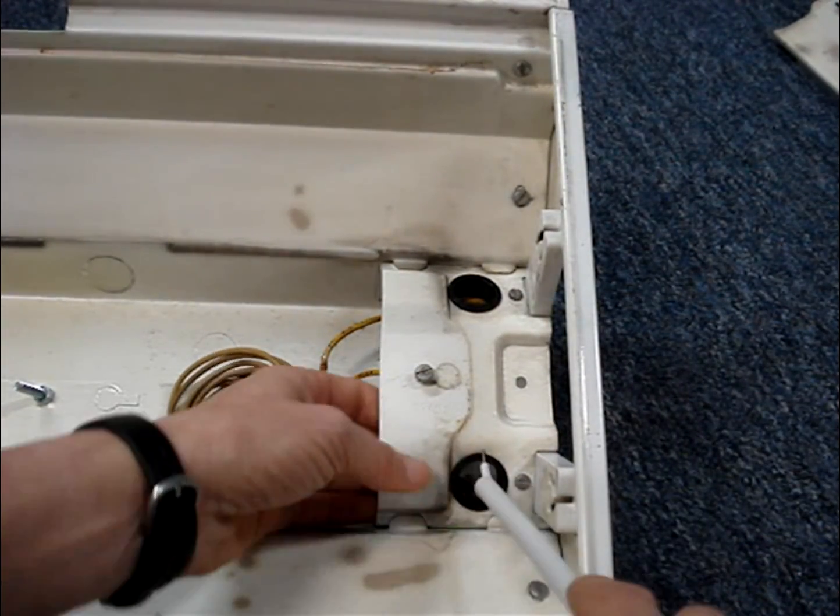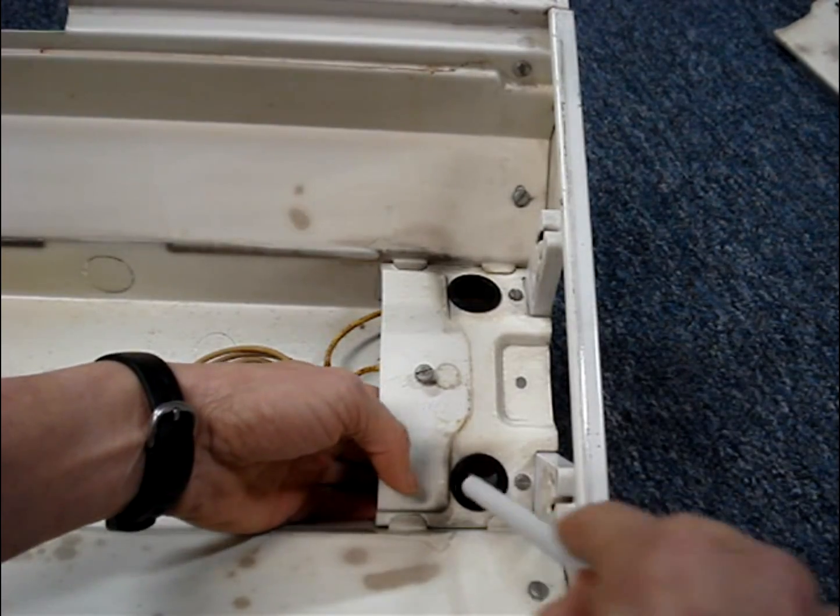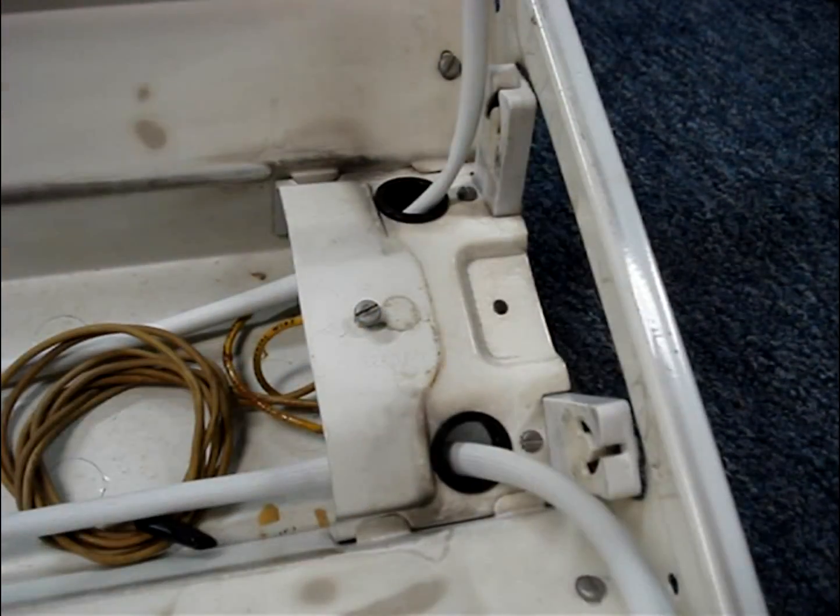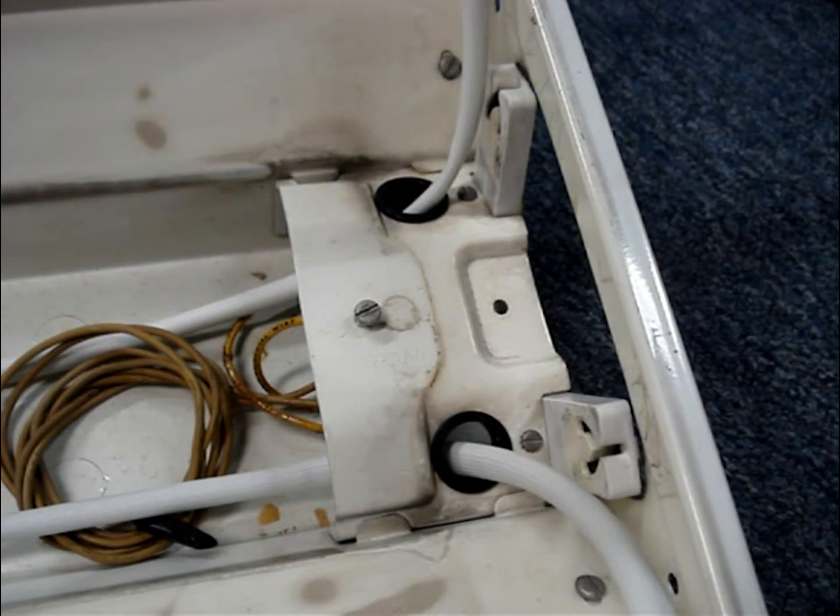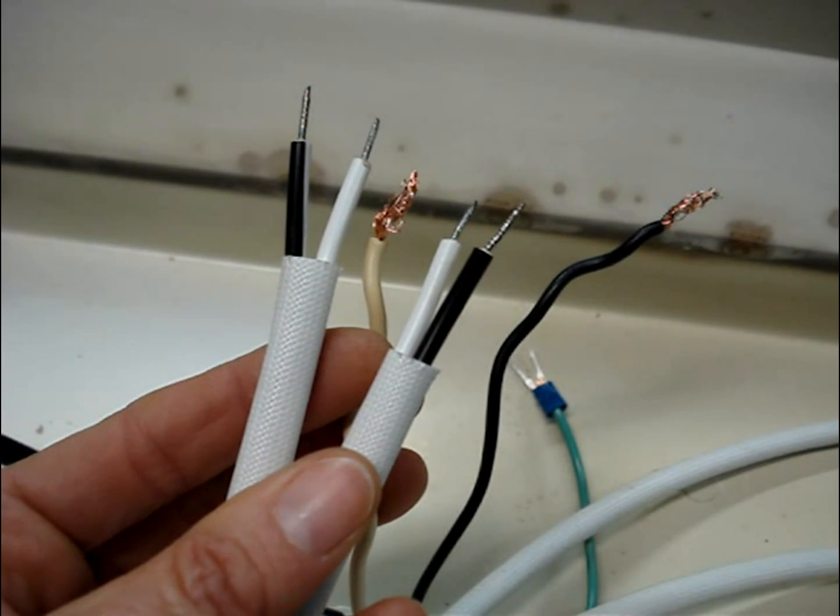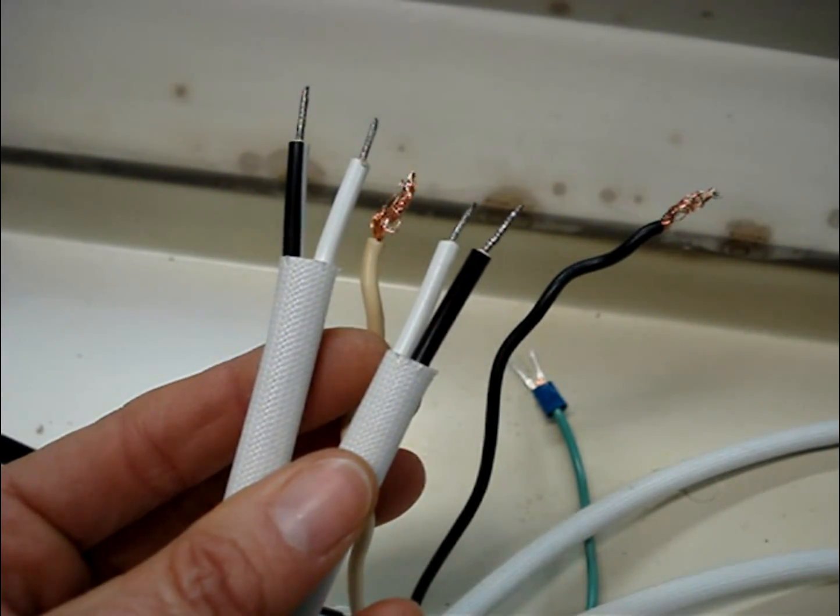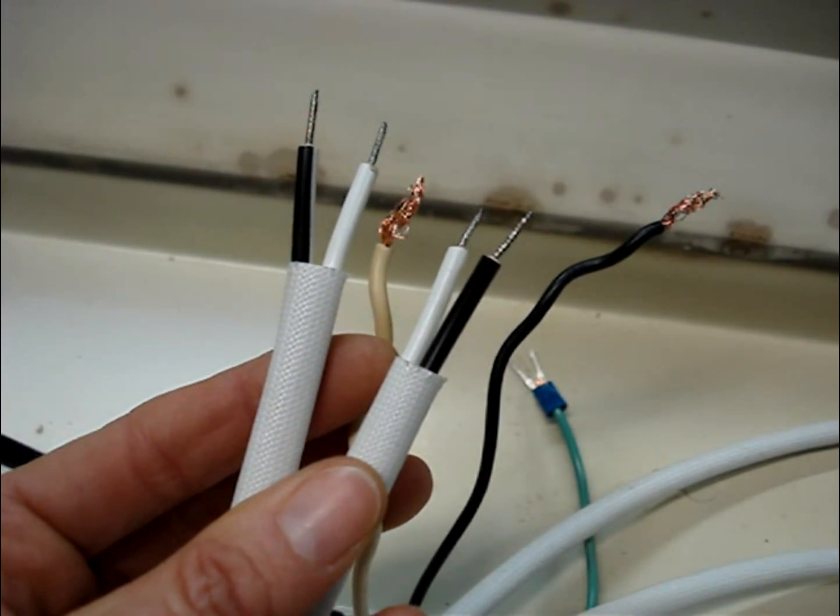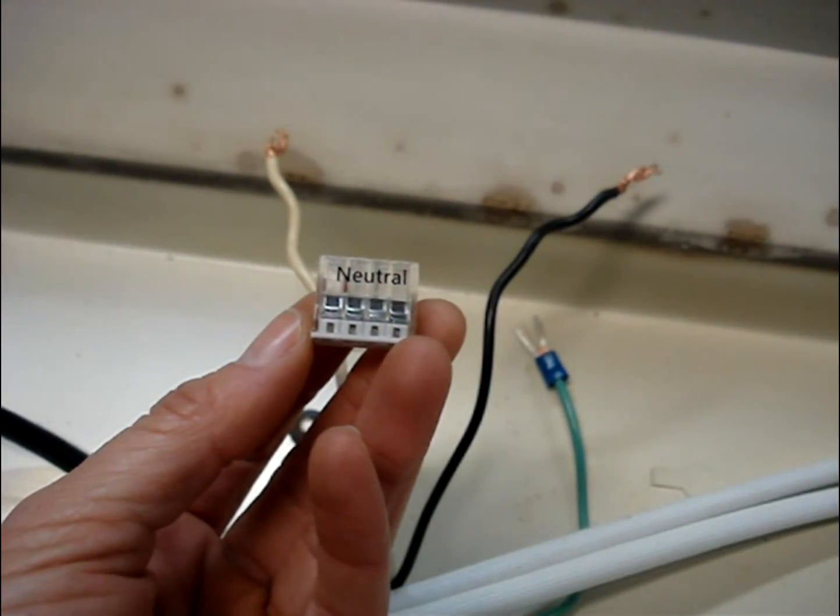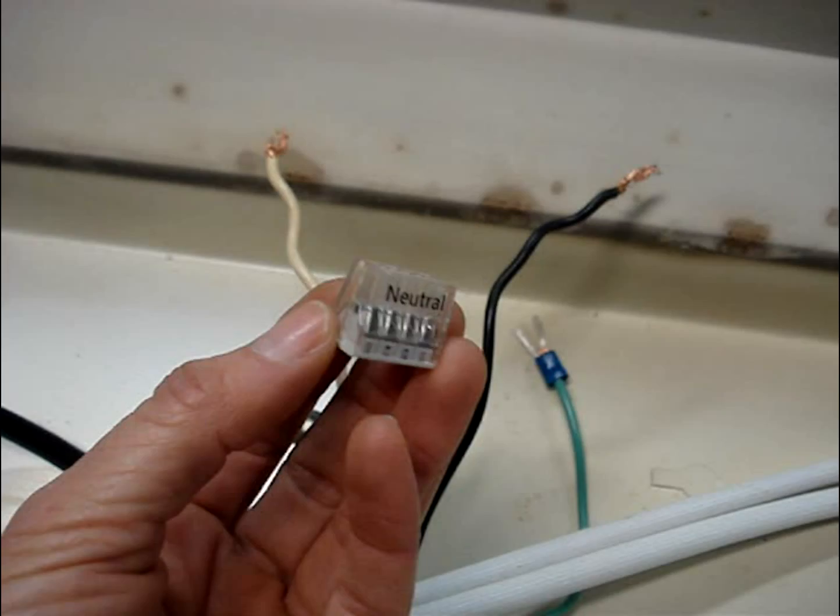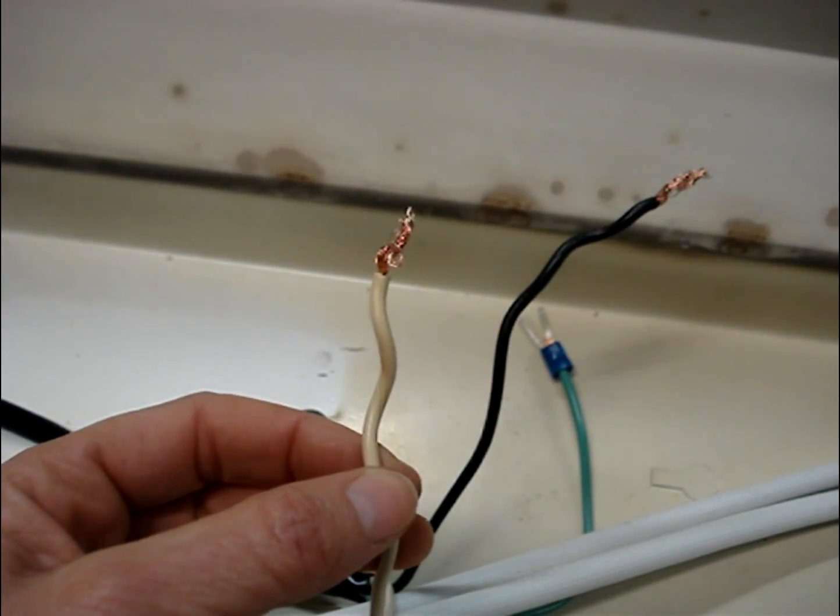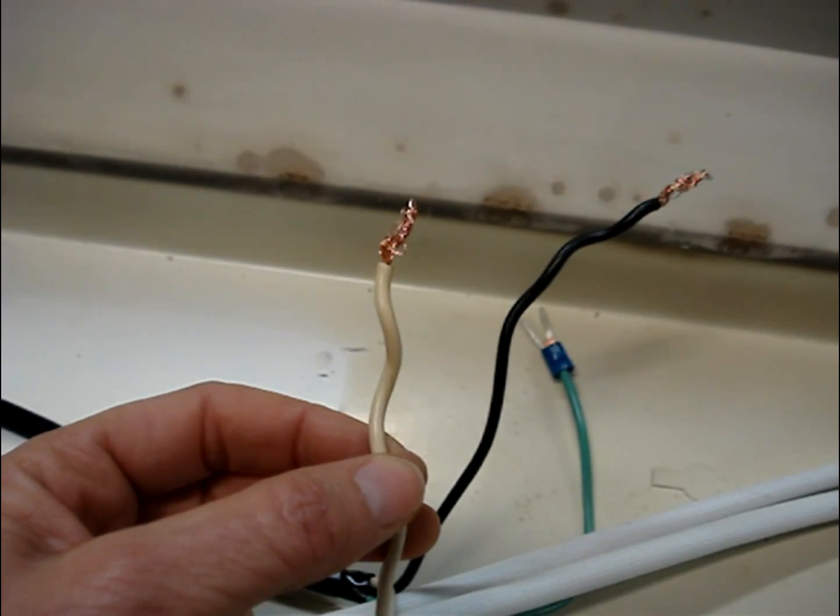Feed the wires from the ends of the LED tubes through the knockouts. Connect the three white wires together, and then connect the three black wires together. The manufacturer supplies you with quick connectors. Because I have stranded wire, I'm not going to use the quick connectors. I'll use wire nuts instead.